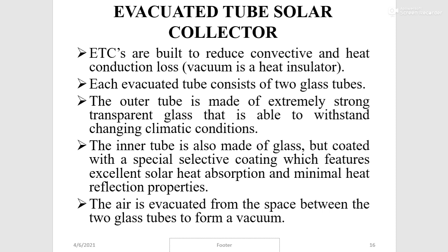Each evacuated tube solar collector consists of two glass tubes. The outer tube is made of extremely strong transparent glass able to withstand changing climatic conditions. The inner tube is also made of glass, but coated with a special selective coating that features excellent solar heat absorption and minimal heat reflection properties. The air is evacuated from the space between the two glass tubes to form a vacuum, so that heat collected at the inner glass cannot escape to the environment.